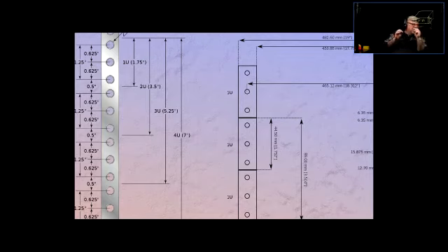And then it's slightly bigger because you have to have some play when you're inserting equipment. You're not going to have watertight spaces there, right? So it's roughly 1.75 inches plus a tiny bit, so you can have a tolerance to mount things properly. All right. So that's a 1U space, right? Some pieces of equipment are going to have 2U spaces. Some of the bigger equipment are going to have 3U. So now you know what the U's are, okay?